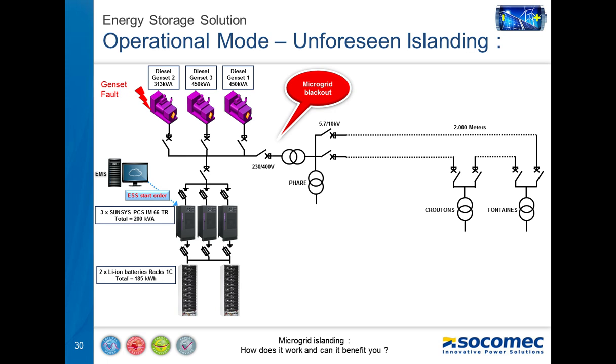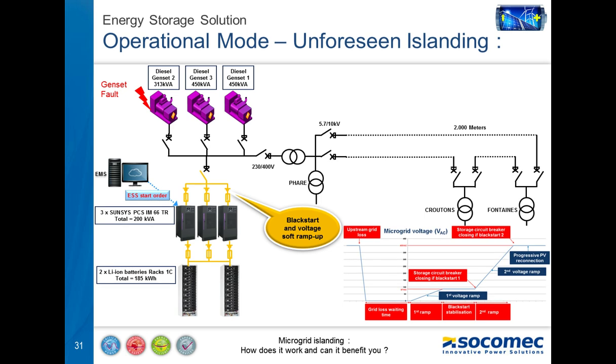Once it's done, the energy storage will take care of the power supply of the entire microgrid as long as the genset is faulty, assuming that there is enough local PV production and the battery state of charge is high enough in order to perform this functionality. The beginning of the sequence is the black start. The ESS starts and then creates, I would say, a soft ramp up of the voltage in order to be able to synchronize all the PCS with each other.